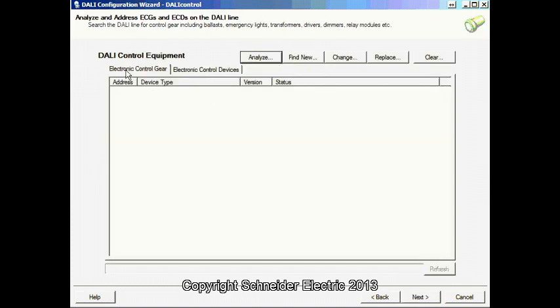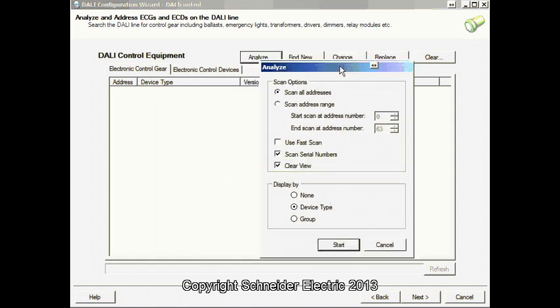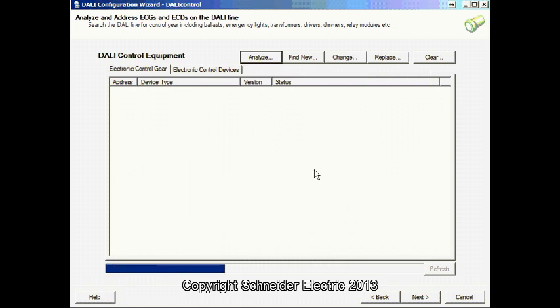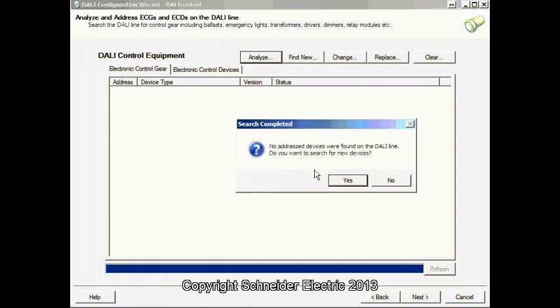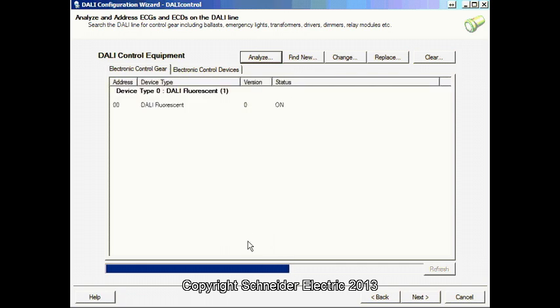Next page, we will be commissioning the DALI control gear. Click on Analyze, scan all address. The wizard will go out and randomly address the fittings, finding one by one and displaying as you see it.